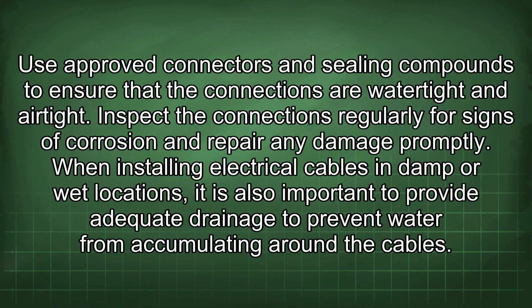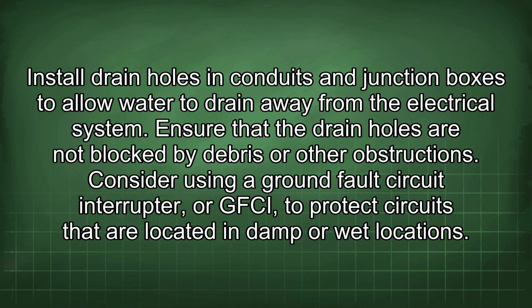When installing electrical cables in damp or wet locations, it is also important to provide adequate drainage to prevent water from accumulating around the cables. Install drain holes in conduits and junction boxes to allow water to drain away from the electrical system. Ensure that the drain holes are not blocked by debris or other obstructions.